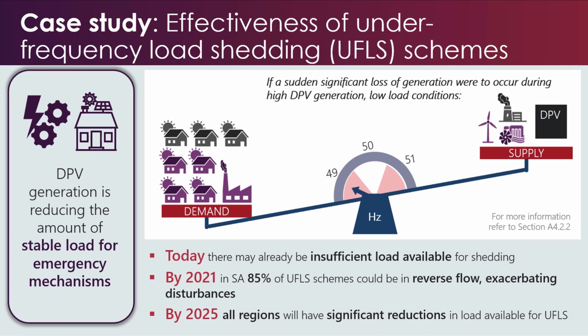This means the supply side may be even lighter, and the scales tip even further into the red, and may mean the system is not stable. This could lead to further load shedding, cascading failures, or in the worst case, a blackout. As more DPV is connected, the amount of stable load available for emergency mechanisms is reduced. Looking at South Australia, which as we noted is already at high DPV penetrations, we have identified that there are periods today where under low inertia conditions, if a large contingency event were to occur, UFLS in South Australia may already have insufficient load to shed to arrest a frequency decline.